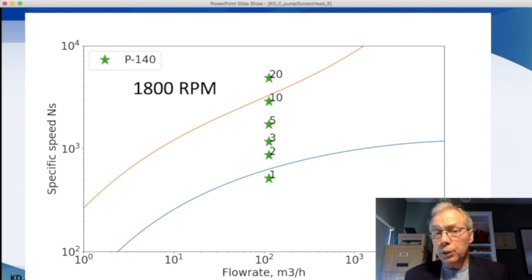Unfortunately, a multi-stage pump is larger than a single stage pump. It takes up more plot space. This impacts the mechanical and civil and the piping disciplines because the equipment is bigger and we may need different pipe routing. Therefore, it is valuable to identify the feasibility of our pump before we approach vendors.